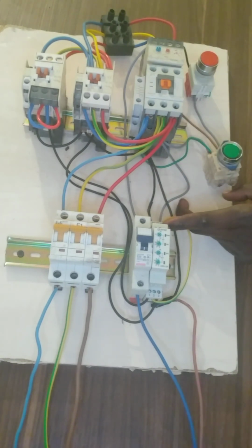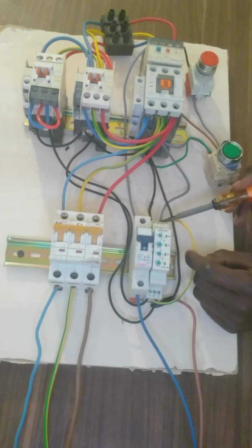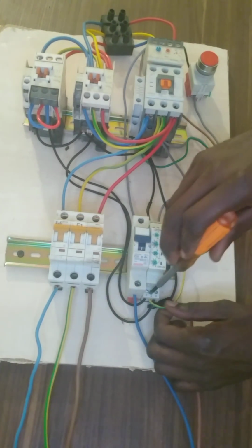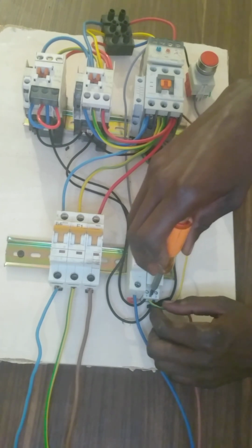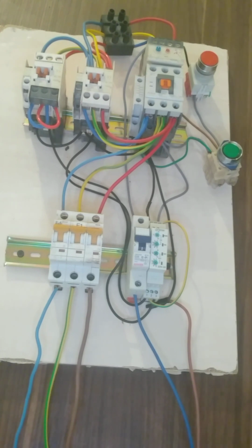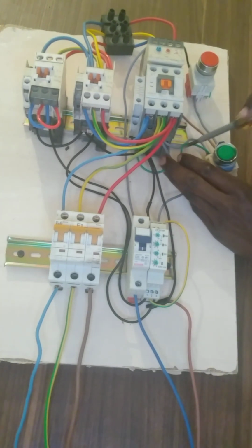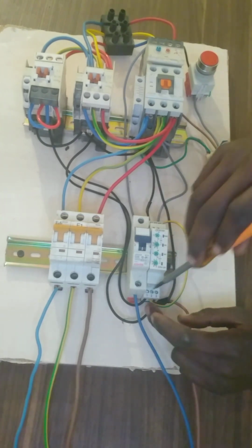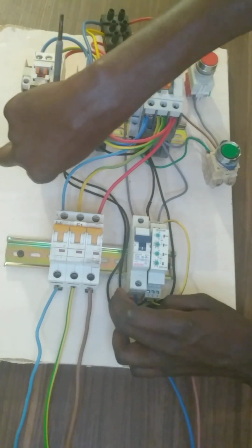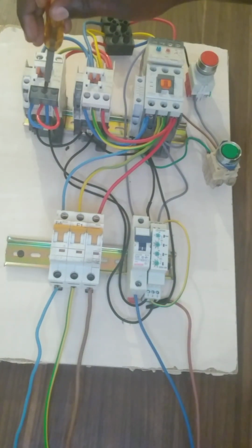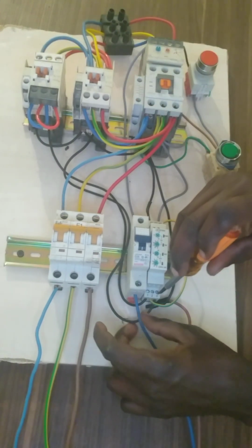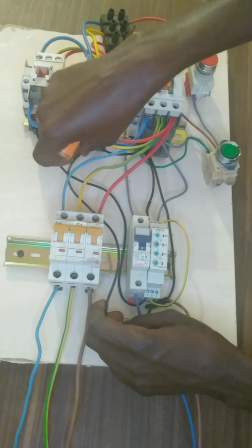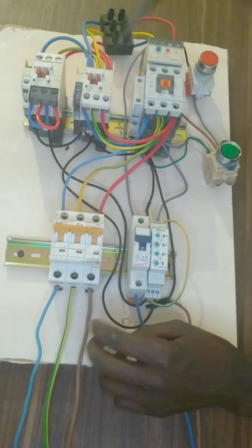A2 is connected with the neutral. So here at the A2 I take a branch to the common point number 2 of the timer. Here, number 1 of the timer is connected to the A1 of the star contactor, and number 3 is connected to the A1 of the delta contactor.